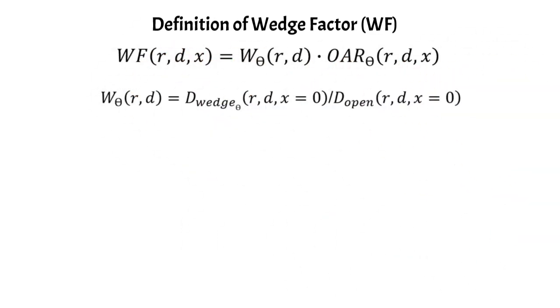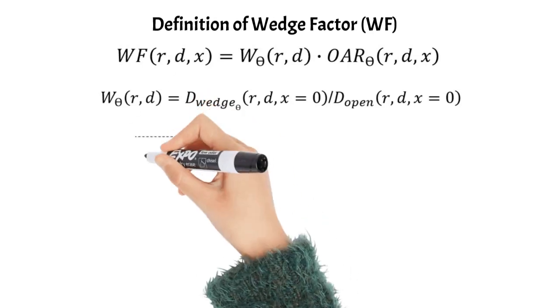The central axis wedge factor is easily measurable, as the second equation shows. We put the wedge in the beam, place the detector along the central axis, and deliver a certain number of MU. Then we remove the wedge, deliver the same number of MU, and take the ratio of those two dose measurements to get the wedge factor. We can also measure the off-axis ratio by measuring a beam profile.